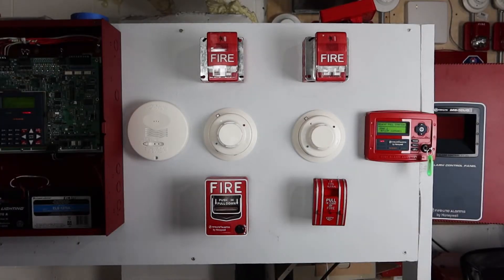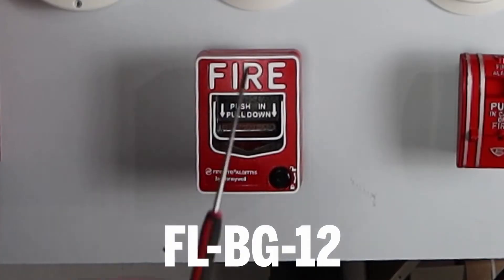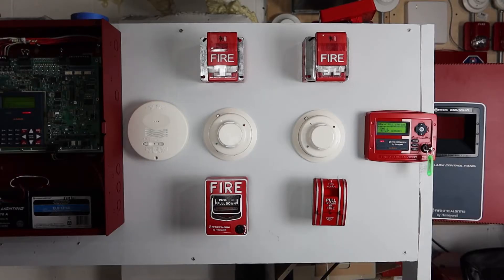Hello everyone. We've had a false alarm due to the pull station on the right, zone 2. As such, we're going to be replacing that with a newer conventional BG-12 — it's Fire-Lite's most standard, most common fire alarm pull station.